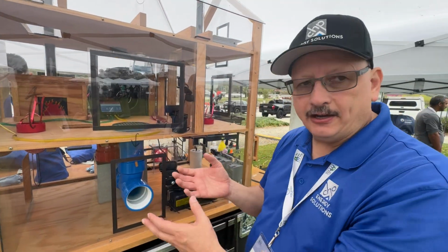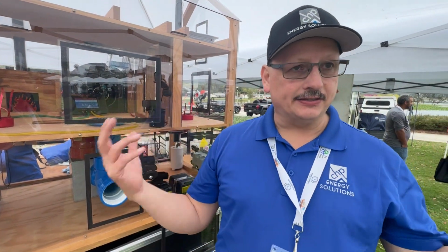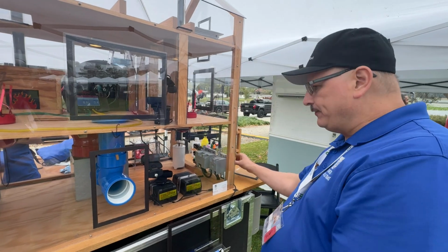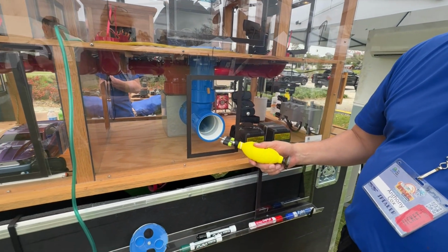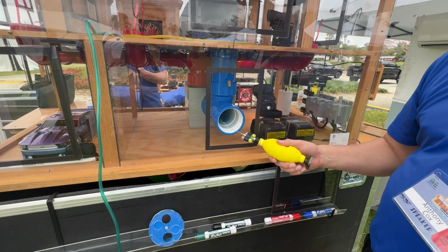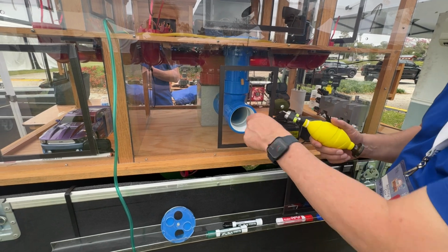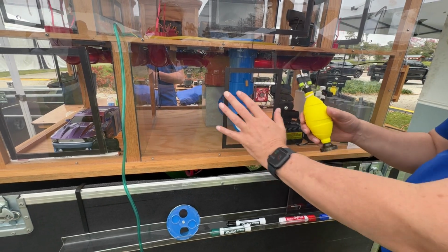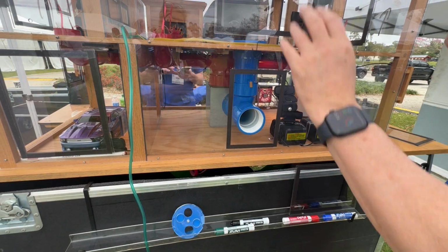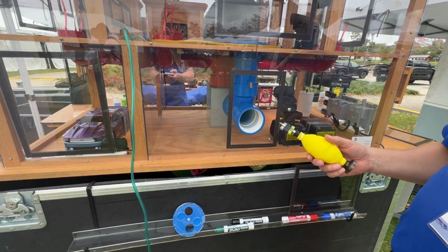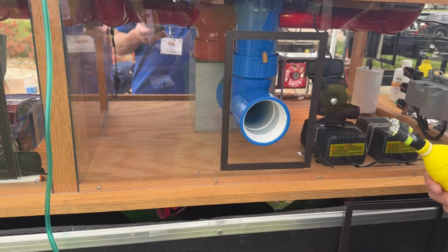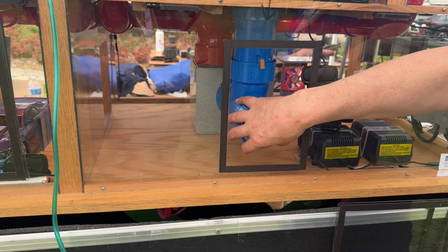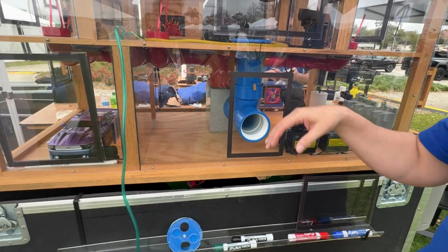Well, the thing is, if you have leaks, in this case it's a return leak. If you watch right here, what's happening to the air? It's going into the house. If it goes in here, into your box, it blows out into the house. So if you have leaks, this is sucking air in. Now this is where the leak itself is, and it might be an attic, crawl space, or basement.